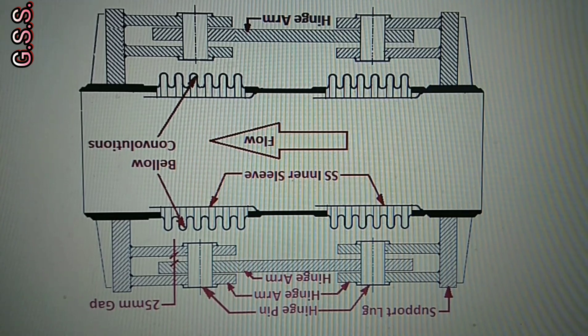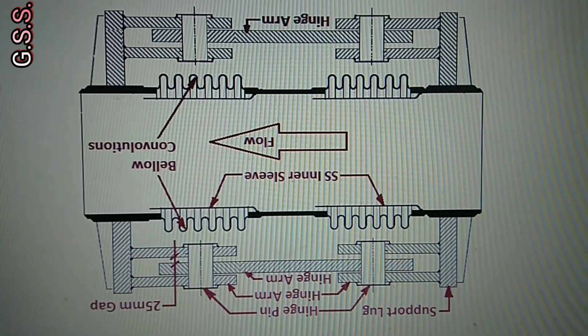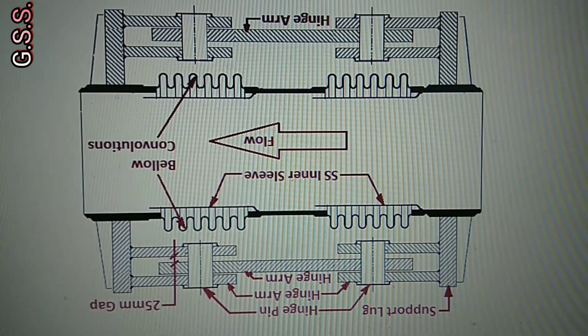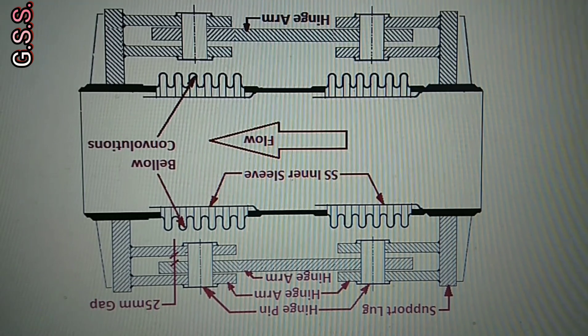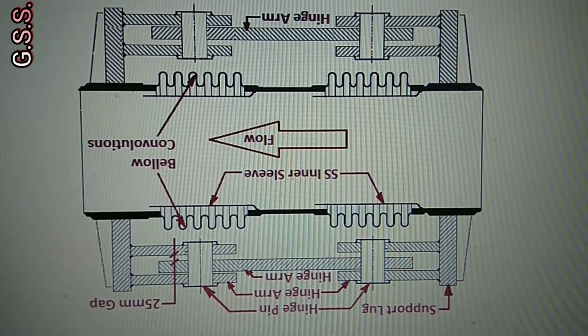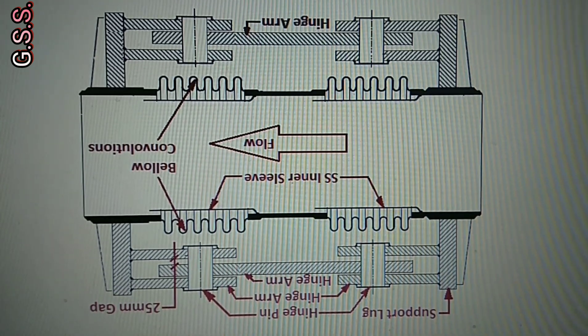This hinge arrangement allows the bellows to take lateral movement only and hinge arrangement is very strong which takes the axial pressure thrust due to internal pressure. There is no chance of expansion of the bellows axially. Hence, there is no chance of transmitting axial pressure thrust to the piping system or to the equipment.